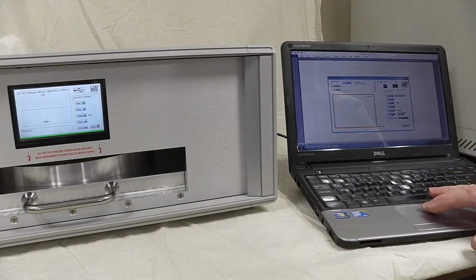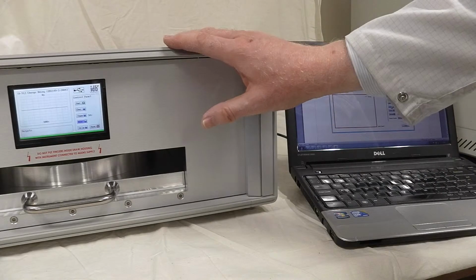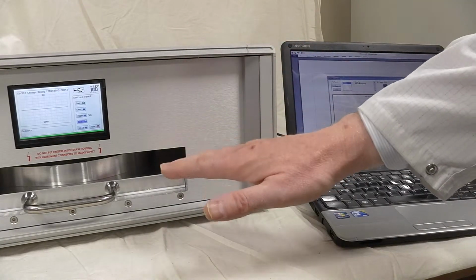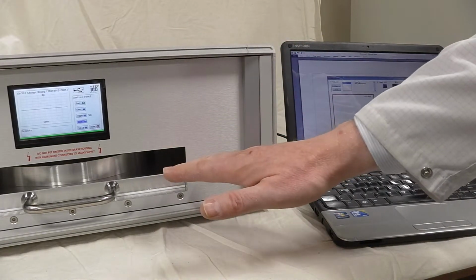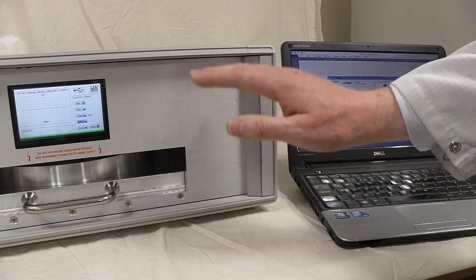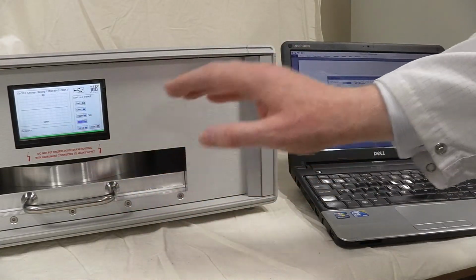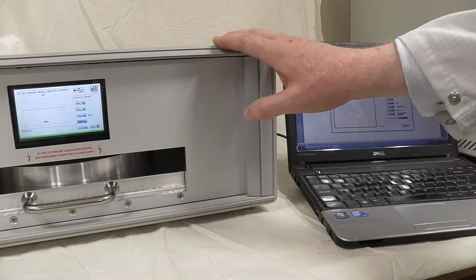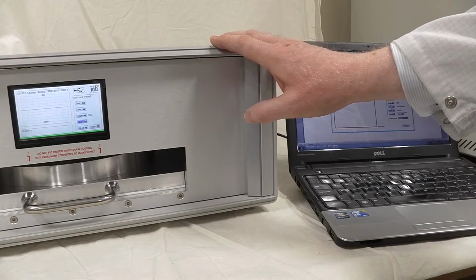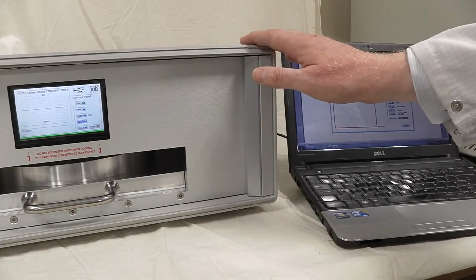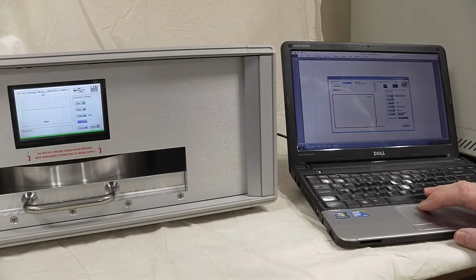been completed. So we now set the Emax button. Remember, we want to baseline the electric field strength in here inside the sample drawer without a sample present. So we want to make a sweep over 30 seconds of what the electric field strength is.